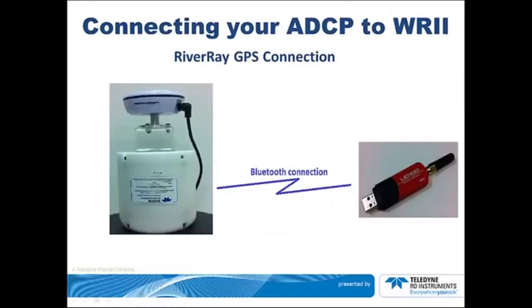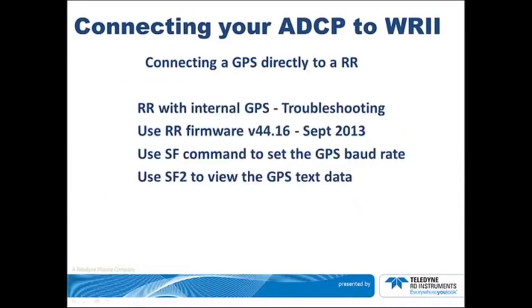In the case of the RiverRay, the GPS is connected directly into the RiverRay via the black cable shown in the picture. Within the RiverRay, the GPS messages are incorporated into the PD0 ensemble data stream and sent over a single Bluetooth connection back to the laptop. For troubleshooting, use the RiverRay firmware version 44.16 which came out in September 2013. Use the SF command to set the GPS baud rate, and SF2 to view the GPS text data.